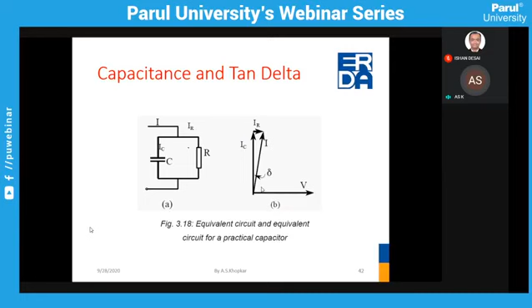So this is the indication that tan delta is increasing. A lower tan delta is better and a higher tan delta is poor for the insulation. It indicates that the insulation is poor or there is moisture in the insulation. That is how we can measure the quality of the insulation by measuring capacitance and tan delta.